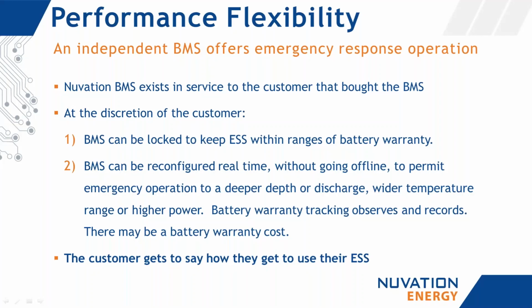So at the discretion of the customer, you could lock the BMS down to functional safety limits of the battery, or lock it down to the energy storage ranges of the battery warranty. Or our BMS can be reconfigured in real time, without even going offline, to permit emergency operation to a deeper depth of discharge, a wider temperature range, or higher power.